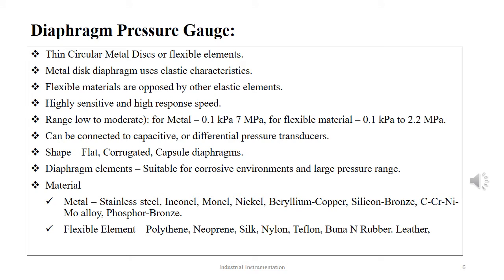The diaphragm pressure gauge is a thin circular chamber either made up of metal disc or flexible elements like rubber, leather or plastic. The choice of the body depends on the purpose of operation. The metal disc body exploits the elastic characteristics of the metal, while the flexible non-metal elements are opposed by other elastic elements. This device, unlike the Bourdon tube, is faster in output response and also has high sensitivity. The pressure measurement range for the metal disc is 0.01 kilopascal to 7 megapascal, and for the flexible non-metal elements it is 0.1 kilopascal to 2.2 megapascal.